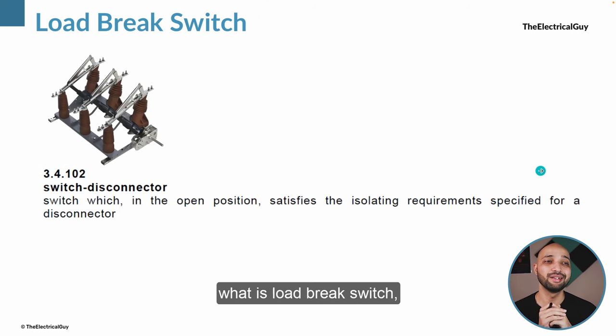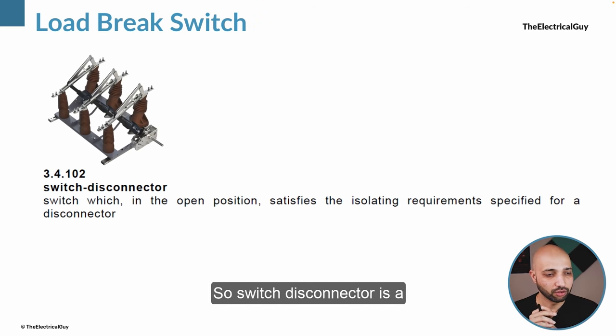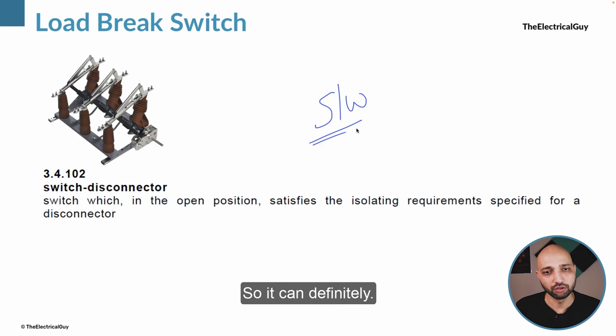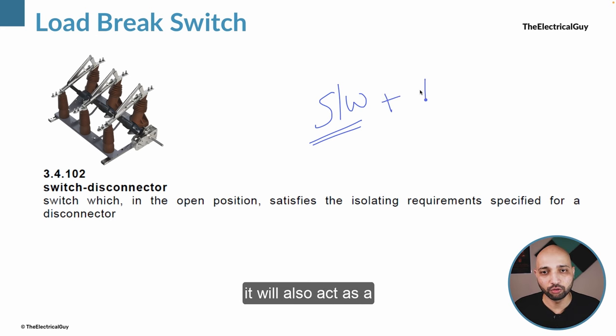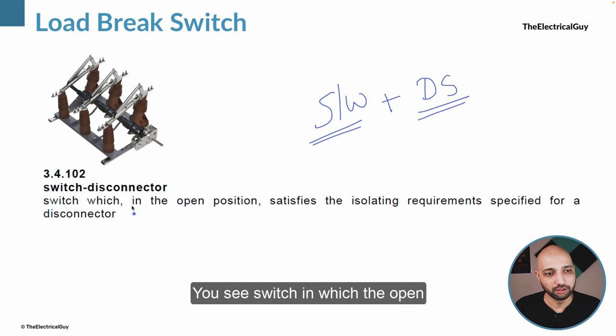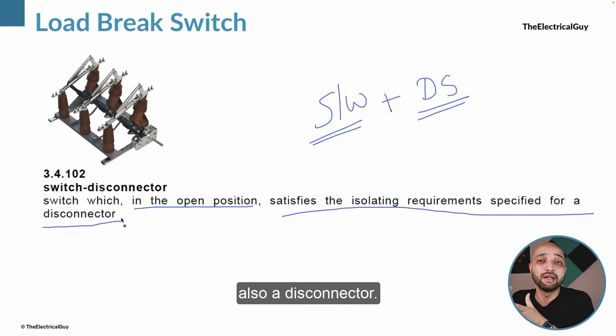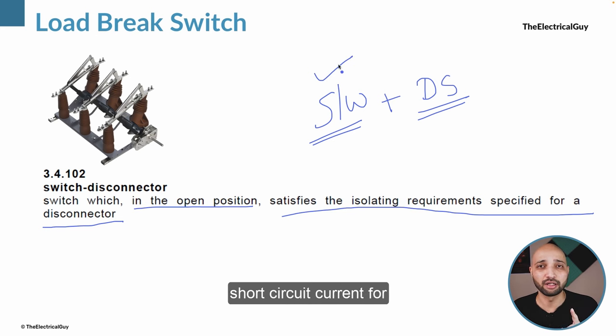Moving on to understand what a load break switch is — IEC calls it a switch disconnector. A switch disconnector is a switch which in the open position satisfies the isolating requirement specified for a disconnector. So it is the combination of a switch and a disconnector: it can make, break, and carry the normal system current, and when opened it will also act as a disconnector. It can also carry the rated short circuit current for a specified time.